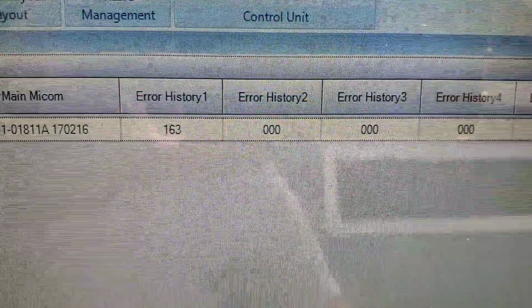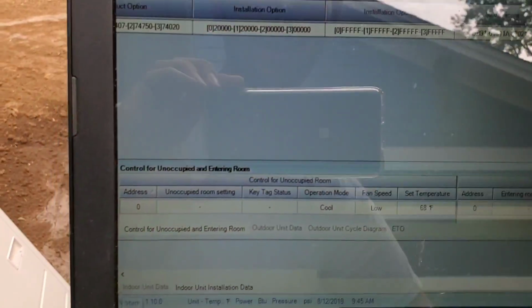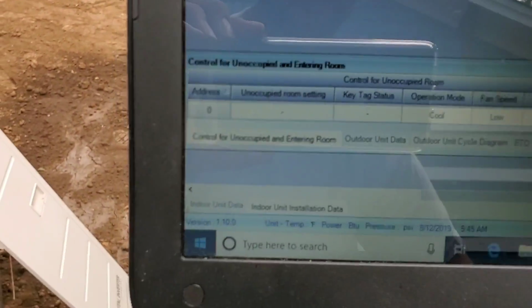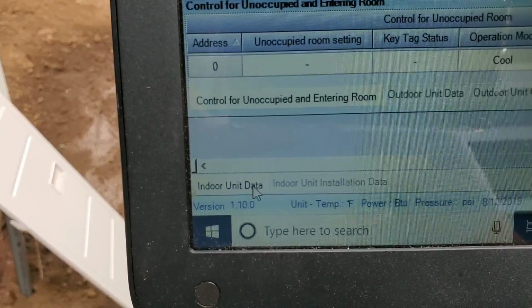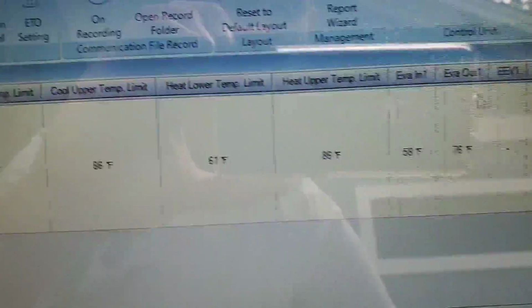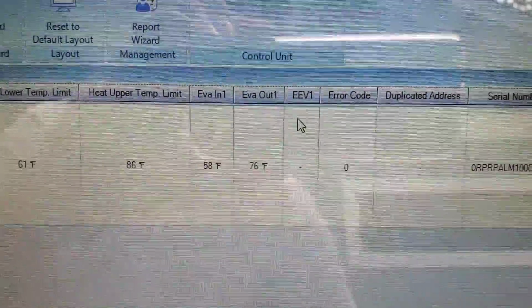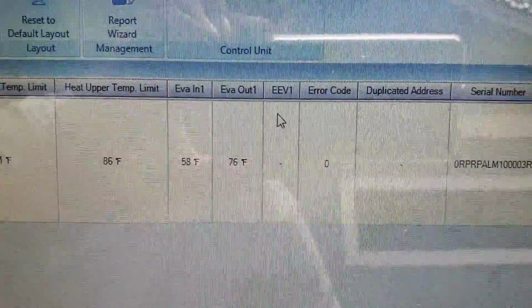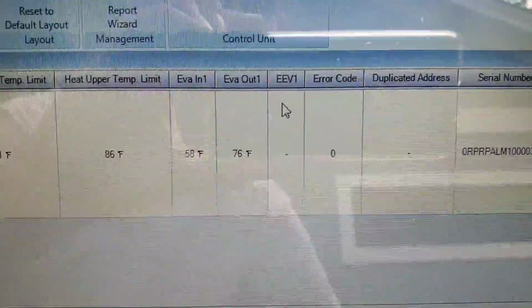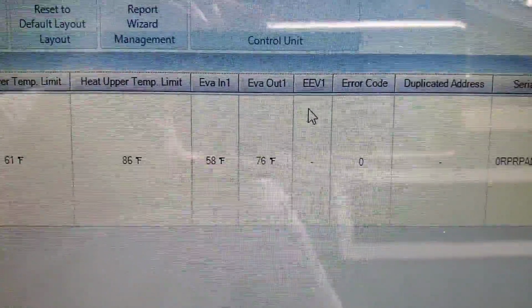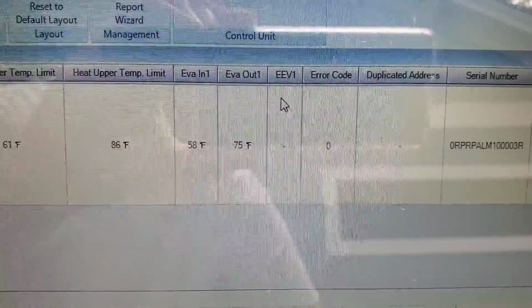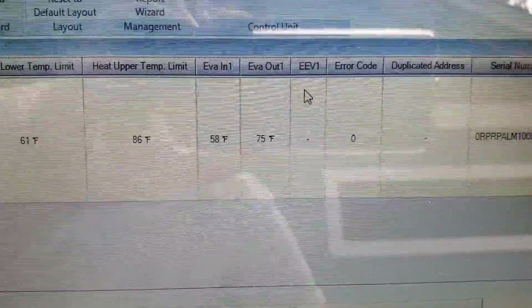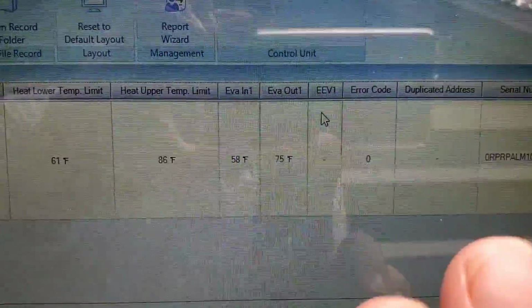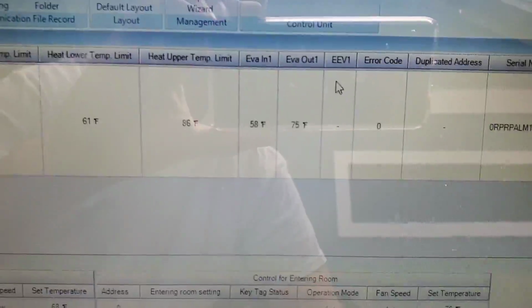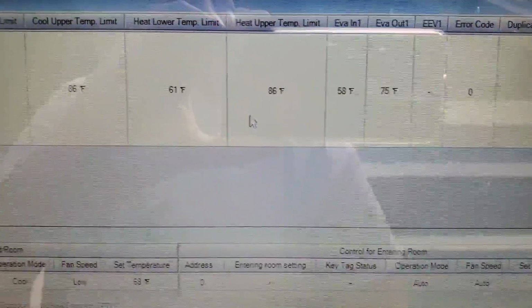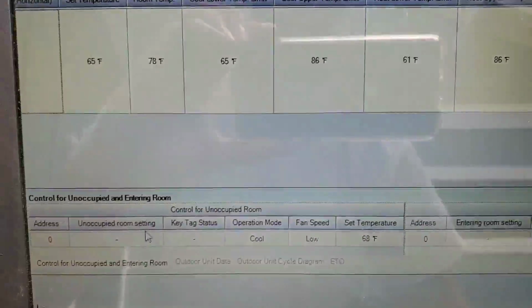Now I'm going to show you how to get to that, error codes. But first let's go down to indoor unit data. I'm able to look at the evaporator inlet and outlet temperature, because there are sensors on the indoor unit. It says the inlet temperature is 58, the outlet temperature is 76. Now that right there is definitely something wrong, because those temperatures need to be really close together. You usually see like a 5-degree difference. So there's something wrong with the charge, I got to check that out.